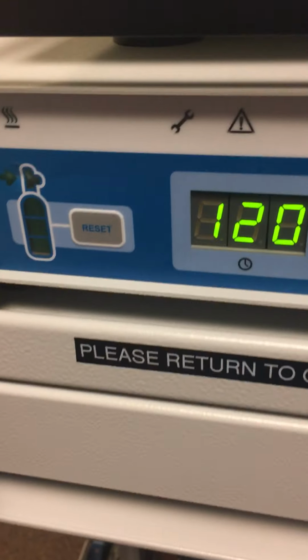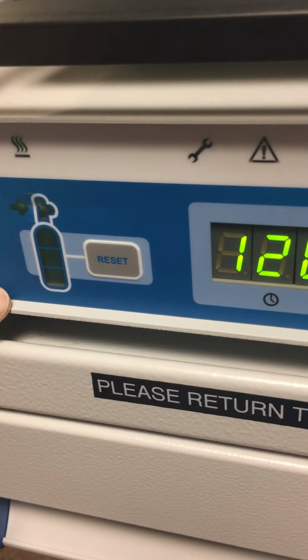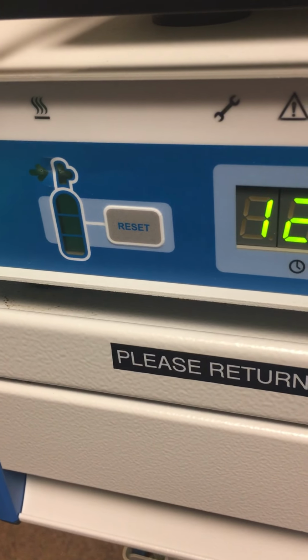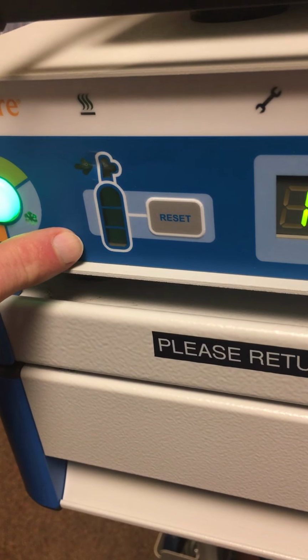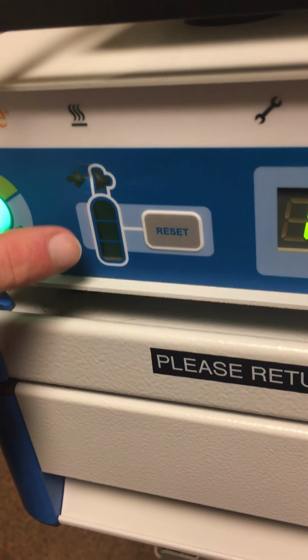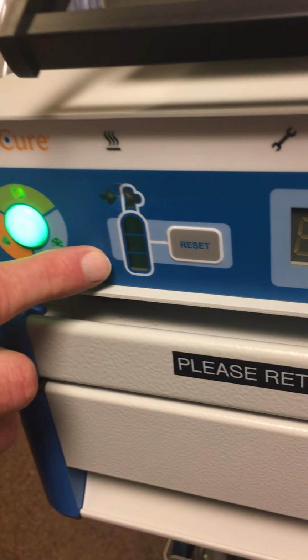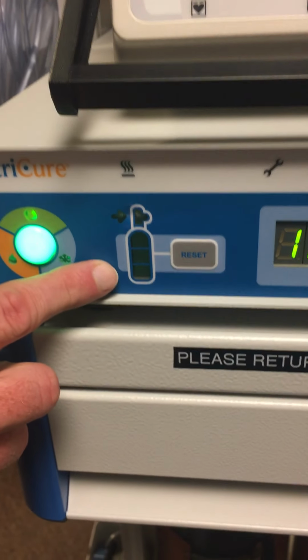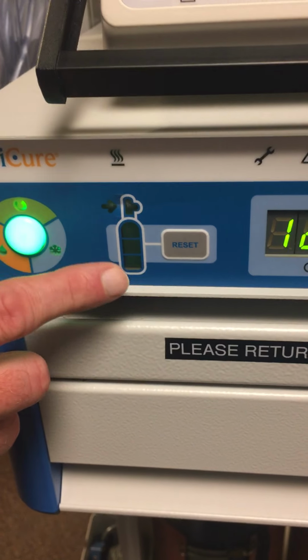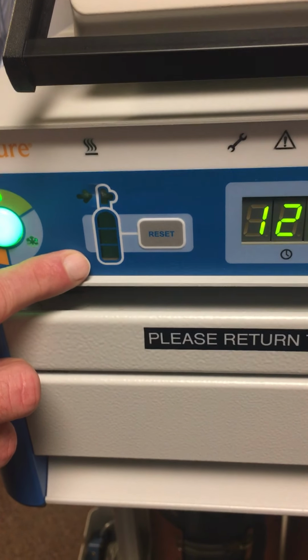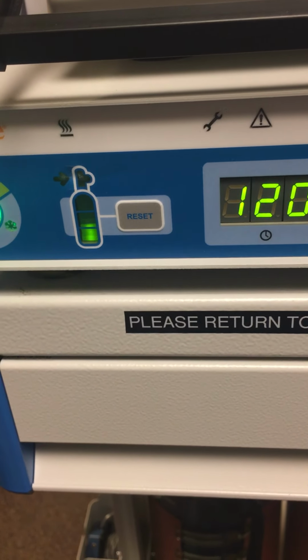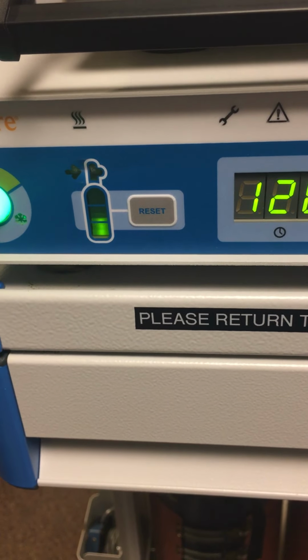Next to that is our tank amount, or pressure amount. With this right here, it's showing we're low. The most important thing to understand about this is that this is only as good as the last person that hit the reset button and changed the tank. So in order to know if you have enough pressure to get through the case, check the pressure gauge in the back, which we started from.